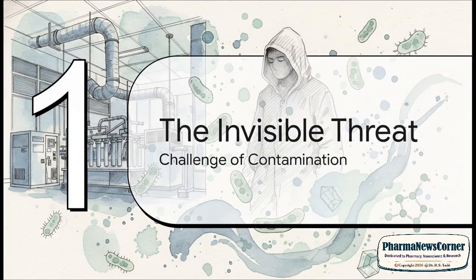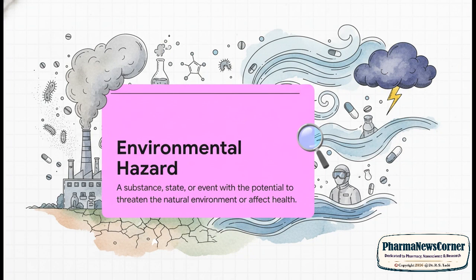To win this war, we first have to understand what we're up against. Let's define exactly what an environmental hazard is and why the air itself is such a huge concern inside a pharmaceutical facility. At its core, an environmental hazard is anything with the potential to cause harm. What's important is that this isn't just about something like a chemical spill - the definition includes a state, like the wrong temperature, or an event, like a power failure. This forces us to take a much broader, more complete view of safety.